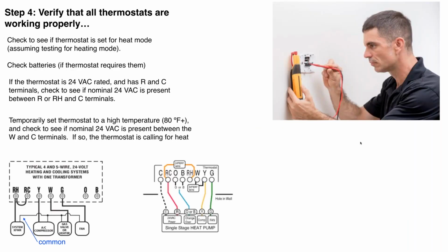Verify that the thermostats are working, to Max's point. Before we start changing circulators and changing other things in the system, check if the thermostat, first of all, is set for heating mode, if it's a heating cooling thermostat. And assuming you're checking it in the heating mode, check the batteries if the thermostat has batteries in them.